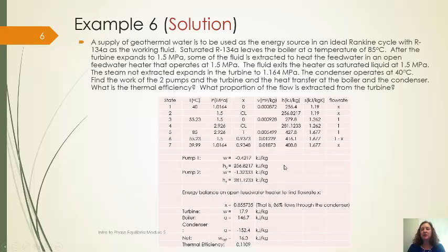If you go through and do these, the first thing I do is I calculate the work of the pumps using V delta P and then use that to calculate the enthalpy at the exit of the pump. But I just have two of those to do this time. Then, go to the open feedwater heater. Once I have all of the enthalpy data, go to the open feedwater heater. That's the new thing. That's the part that you have to now do a new sort of balance and figure out what's the split between the streams that are bypassing the end of the turbine. That energy balance on the open feedwater heater will allow me to calculate X. I've done that and it says that 85% of the stuff flows through the condenser and so about 15% flows just directly into the feedwater heater.